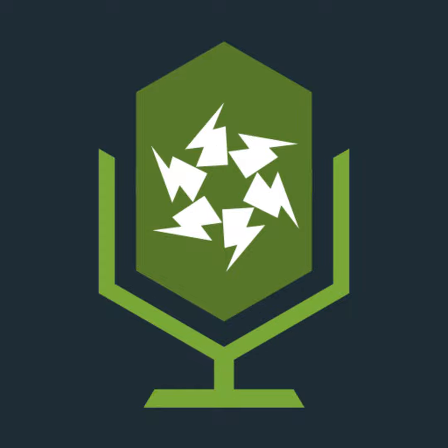So if we go back to Appendix 4, and again, there's an awful lot of Appendix 4 backwards and forwards here. In fact, at this point, let's cover this. Go to the beginning of Appendix 4, page 373. It gives you a list of all schedules, and the rating factors are kind of previewed there. 4B1, rating factor for ambient temperature. 4B2, rating factor for ambient ground temperature. So there's mention of the rating factors there now.